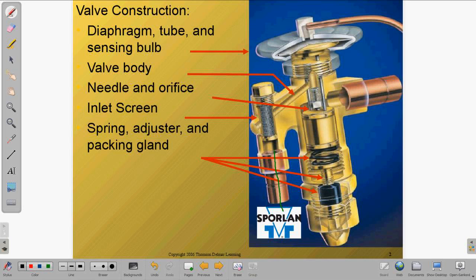A couple of things. This is the diaphragm up here, and this is part of the opening force of the TXV, and we'll look at this again in more detail. These pins are connected to the bottom of the diaphragm, and it pushes down on the piston. So that's your downward and opening pressure, and then we have the suction line pressure pushes up on the bottom of the diaphragm, and we have spring pressure. So we have three different pressures that open and close the TXV valve.